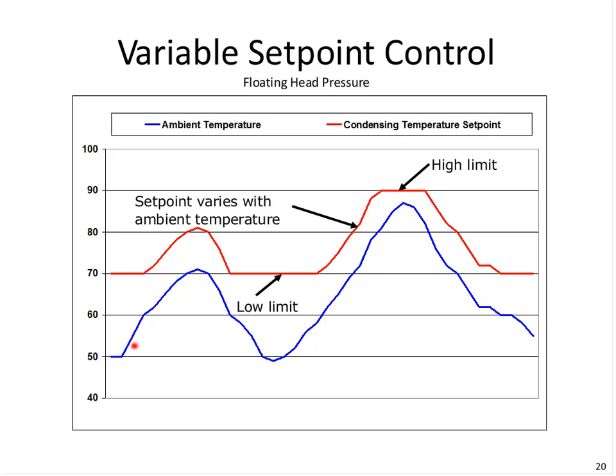Now notice as the day comes along and we get up to a 60-degree ambient, now we've got about a 10-degree difference between condensing and ambient, and then we're just following along here. So the set point would go right on up with the ambient. Here's the peak of the day, so a 71-degree day, 81-degree condensing, and then we would have our set point continue to adjust to the low limit. Notice the next day here, we're getting a warmer day. The ambient's maybe going up to close to 90 degrees, and notice all along here it's about a 10-degree temperature difference. Then right here the ambient is 80 degrees, the condensing temperature is 90, and notice it says high limit. And when the control system detects the high limit, this just implies that we're going to have the fans running at full speed.